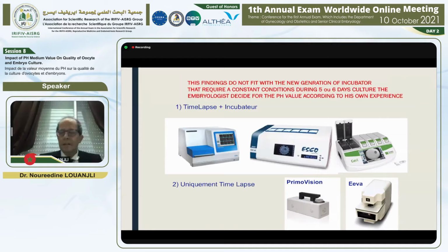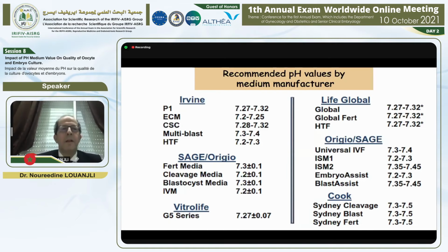This finding doesn't fit with our daily practice, because the new generation of incubators needs a stable condition, one condition for 5 or 6 days. The embryologist decides the pH value according to his own experience, 7.25 to 7.30, so as not to modify it, because the target of this new generation of incubator is to keep homeostasis stable and not to modify product and incubator. We have to choose one value of pH during all culture. The values recommended by the companies are in general between 7.2 and 7.4, but every company has little changes according to the concentration of bicarbonate.